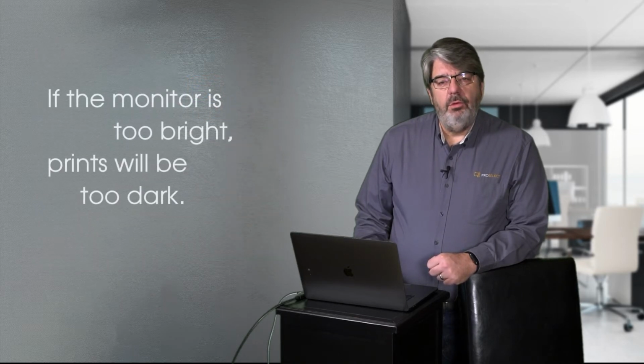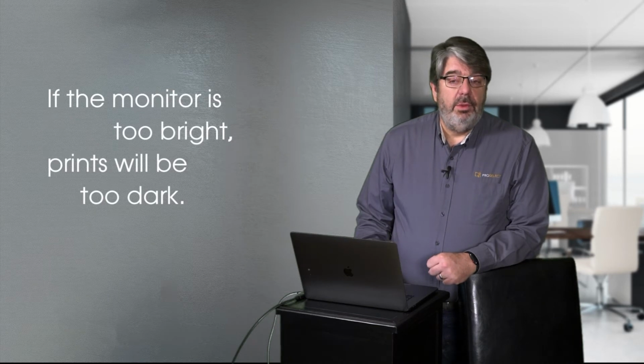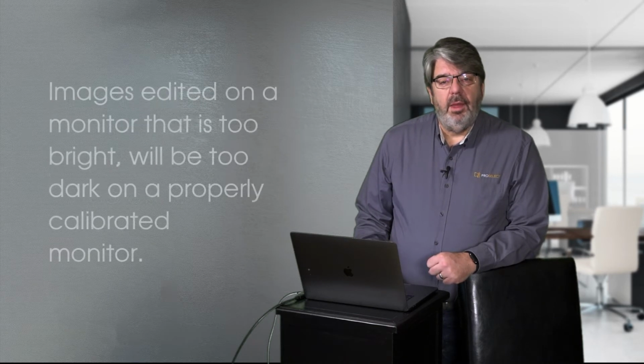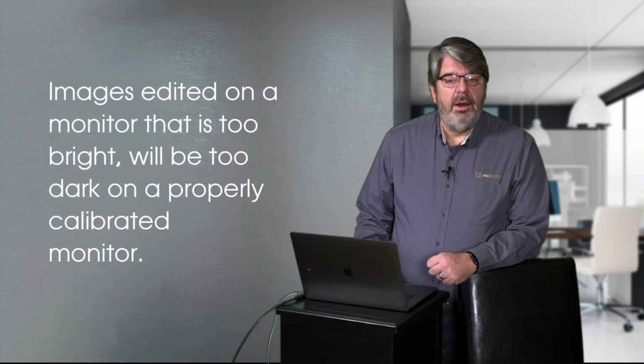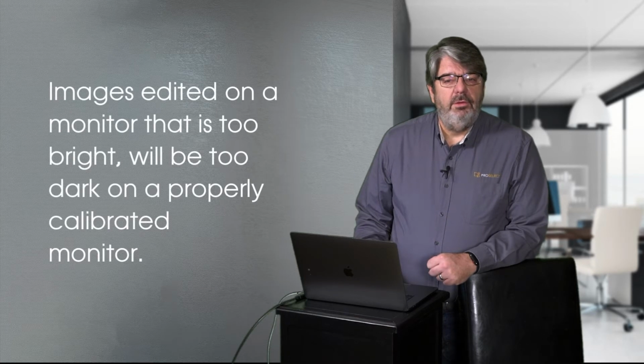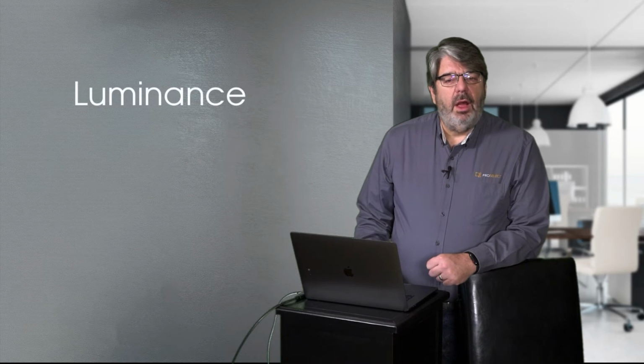Luminance is critical. If your monitor is too bright and you adjust your images at that full setting, when they're printed, they will be too dark. In the same respect, if images are judged or reviewed on a monitor set to a lower luminance, they too will display darker than really what you intended. Highlights will be muted and shadows will be blocked up. For the luminance setting, we want to use 120 candelas per square meter.